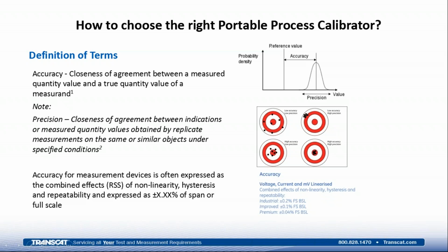So for our voltage, current, and millivolt output pressure sensor devices, we state that the combined effects of nonlinearity, hysteresis, and repeatability are, for example, for the industrial grade, plus or minus 0.2% of full scale, and BSL refers to a best fit straight line, which is a definition of the comparison of those points together. I'll go into a little more detail on the definition of nonlinearity, hysteresis, and repeatability on the next slide here.